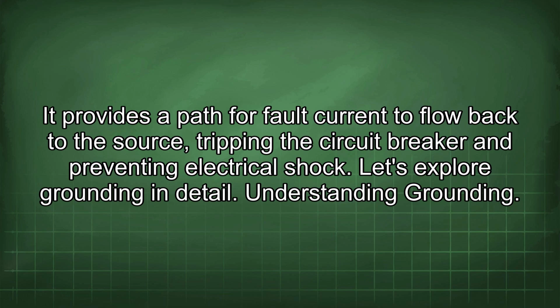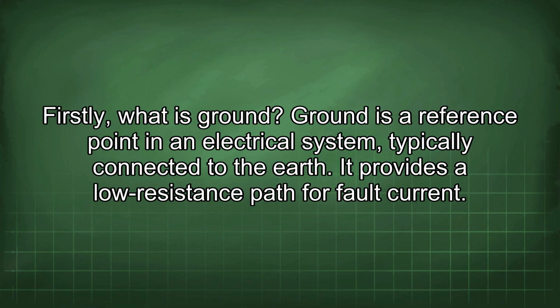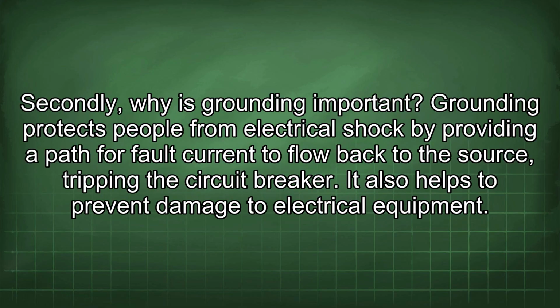Understanding grounding. Firstly, what is ground? Ground is a reference point in an electrical system, typically connected to the earth. It provides a low resistance path for fault current. Secondly, why is grounding important? Grounding protects people from electrical shock by providing a path for fault current to flow back to the source, tripping the circuit breaker. It also helps to prevent damage to electrical equipment.